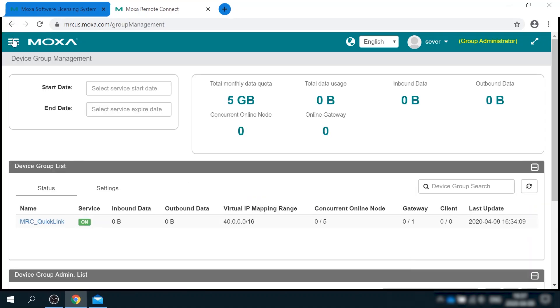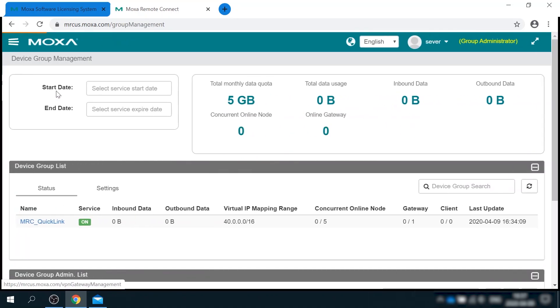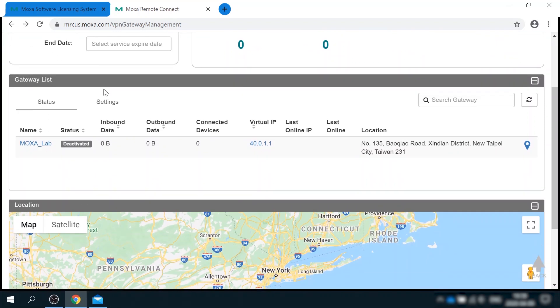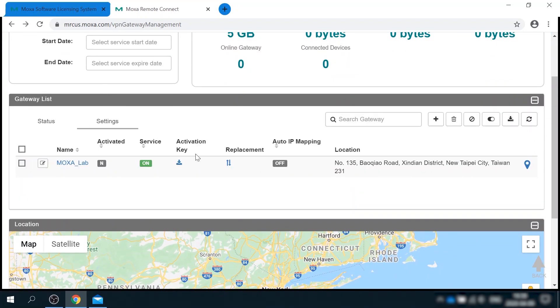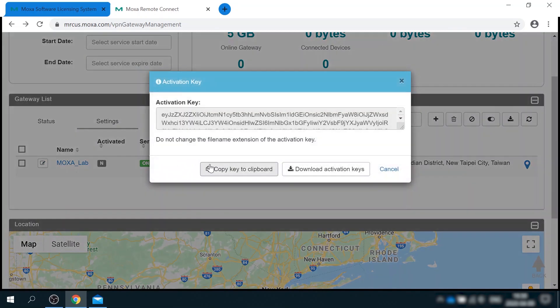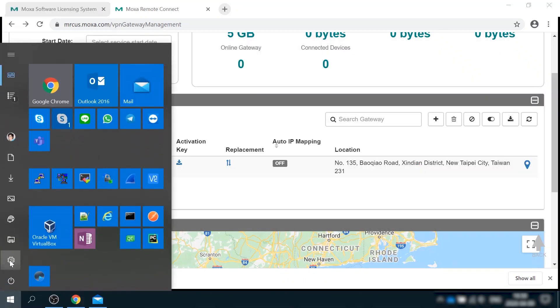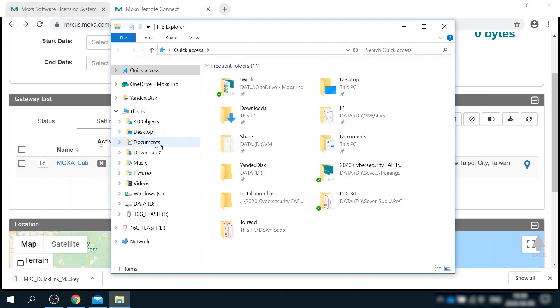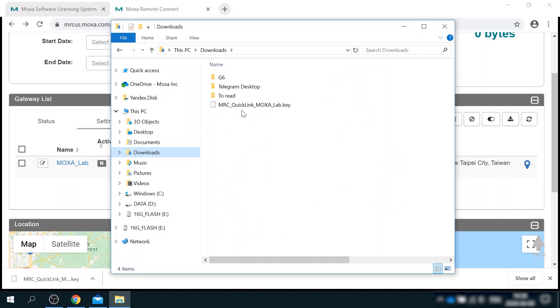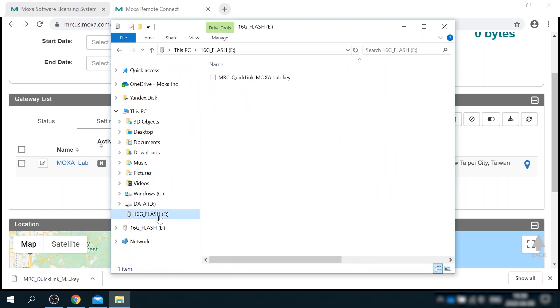Now I can go to gateway management menu. And here I can see Moxa lab gateway that I've just configured. Its current status is deactivated. So what I need to do is to click on activation key here and download the key. I'm putting this key file on my USB thumb drive. And now I'm ready to deploy the gateway in the lab. So I'll head to the office and do it.